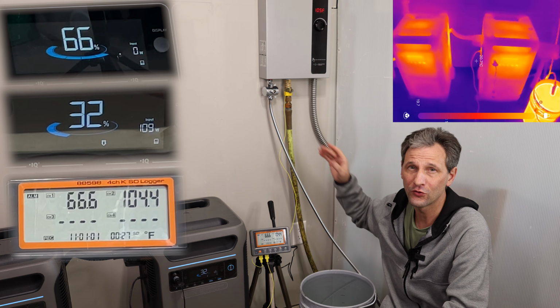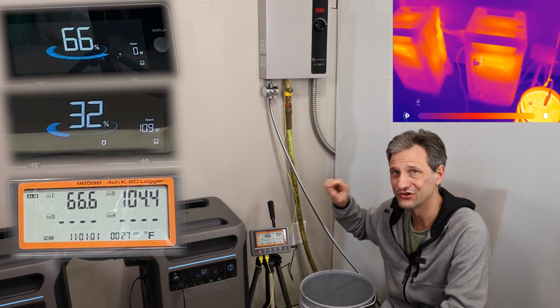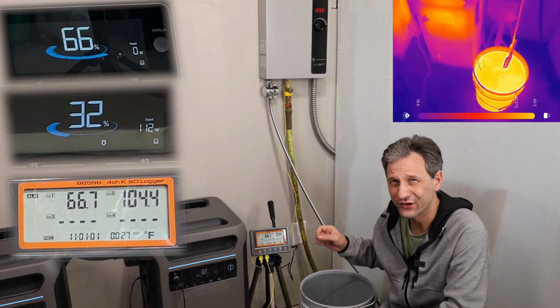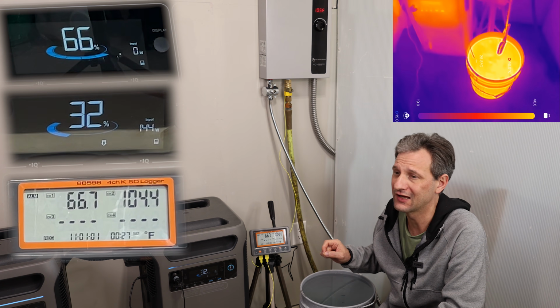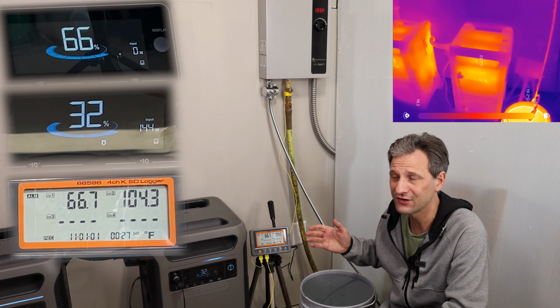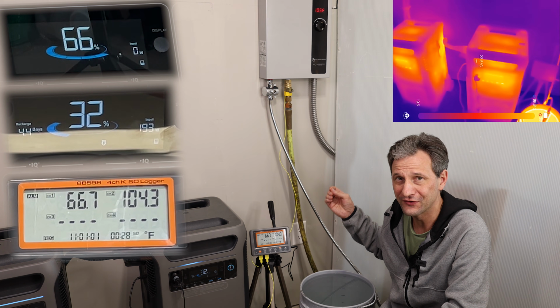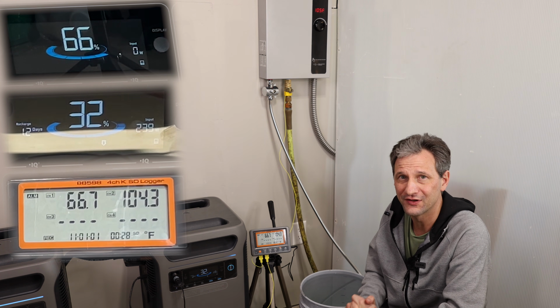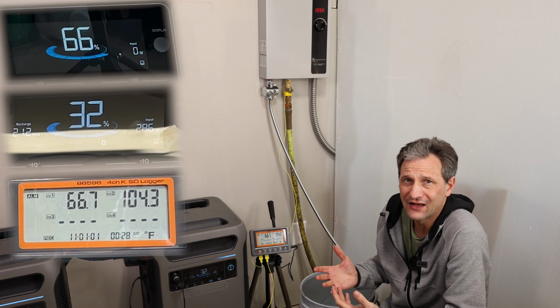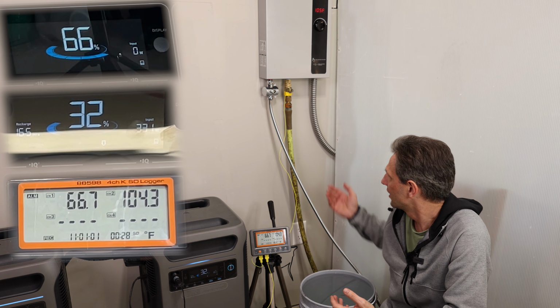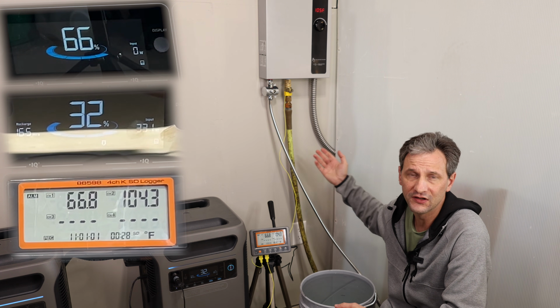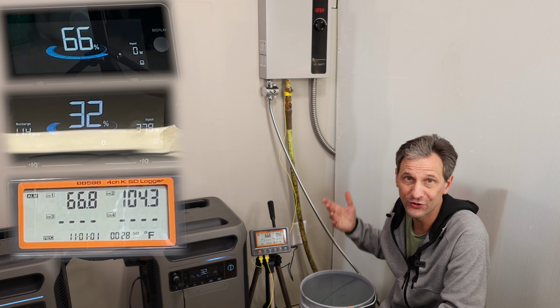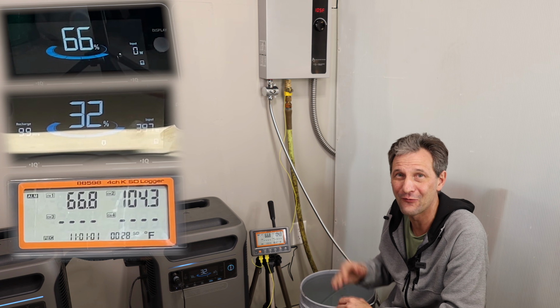This thing's rated for a 35 degree temperature rise at just over 2 gallons per minute. I was running just under 2 gallons per minute, and I was getting over a 40 degree temperature rise. So that's pretty impressive, I'd say it pretty much meets what it says it can do. It's actually sufficient, especially if you were running a hose into this and coiled the hose outside in the sun before running it in, you could get some really hot water from that.